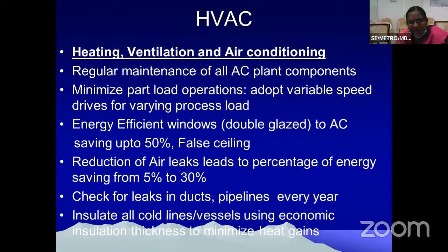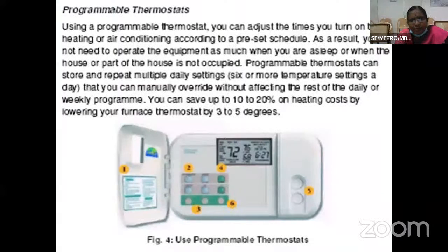Reduction of air leaks leads to an energy saving of 5 to 30%. Check for leaks in ducts and pipelines every year. Insulate all cold lines and vessels using economic insulation thickness to minimize heat gains. Programmable thermostats can also be used to adjust the times you turn on the heating or air conditioning according to a preset schedule. Smart air conditioners have come in. You can even control the air conditioners from your mobile.